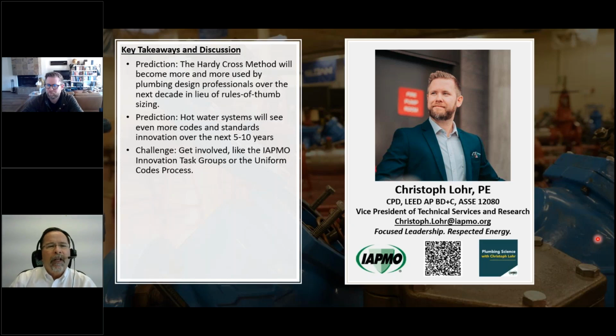Yeah. So really, for the client, the documentation to prove that the system was installed according to the design and is working properly might be more of a commissioning report that says the temperatures were checked. Yes, all the fixture piping is up to temperature, and the system is functioning as designed. Okay. Yep. So I would say the testing and balancing is separate from the commissioning, and so all balancing valves, automatic or manual, should be commissioned. You should make sure that the system works. Some third party probably should come in and double check it. But when you have a manual valve, you need the testing and balancing, whereas with the automatic, you don't.